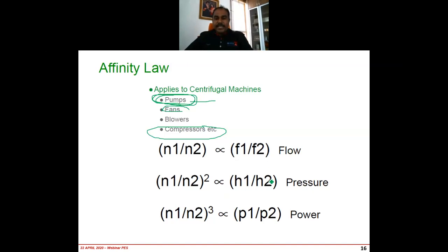And what is affinity law? Affinity law says that when there is a reduction of the speed, your flow is proportionally reduced. Similarly, when you have a reduction in the speed, you have a reduction in the pressure with a square relationship, the speed squared. And the most important thing we have to look at is this: when there is a change of speed, the power reduction can be very huge because the relationship is cube. Can you see that?